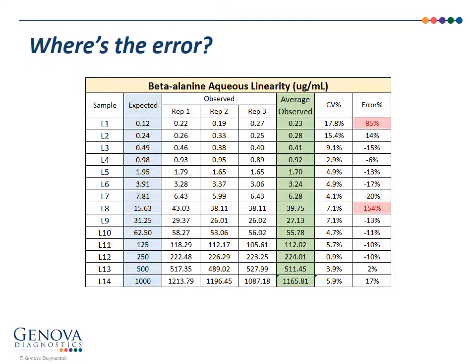You know, we made 14 dilutions. That particular tube, maybe we accidentally double shot it. I mean, it got contaminated. I'm not quite sure, but it's reproducible. So in this case, I would drop out level 8, repeat just that line, and see if that improves your error.